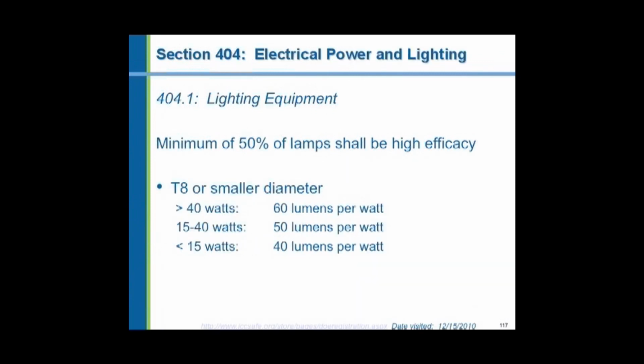Now we talk about this term called efficacy. We've mentioned it a couple times before. What is it? Well, it's defined back in Chapter 2, and it basically means efficiency. However, efficiency varies with the wattage of the lamp. Small lamps are less efficient, large lamps are more efficient, and the code recognizes that and approves it.